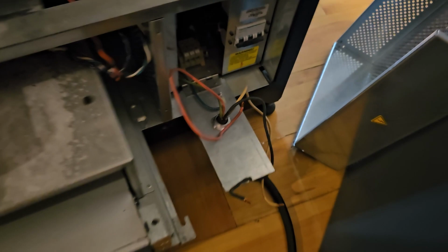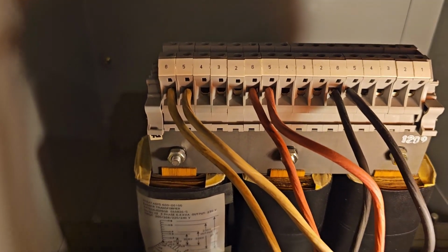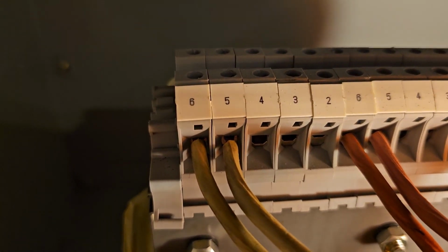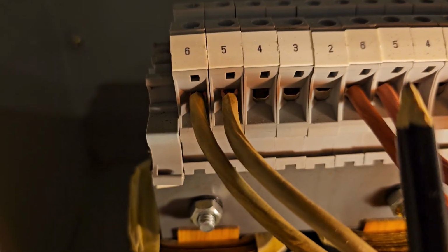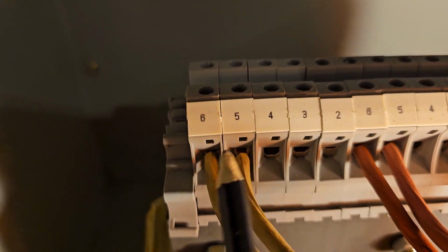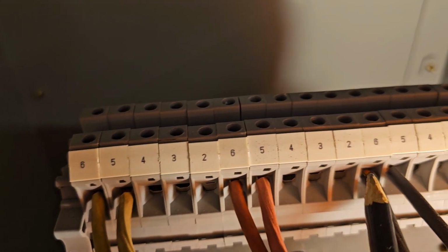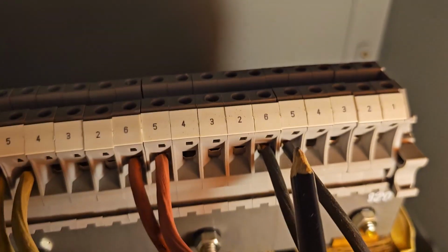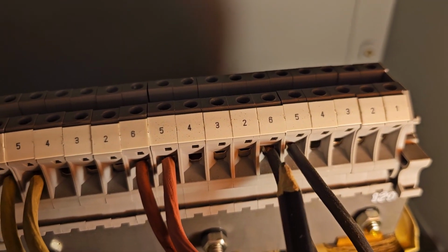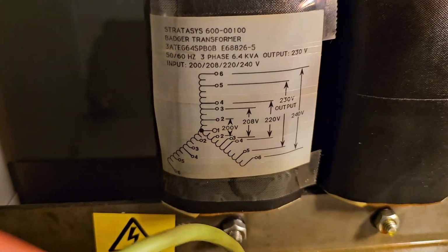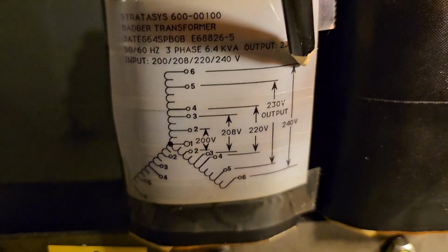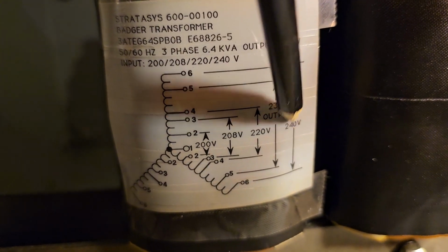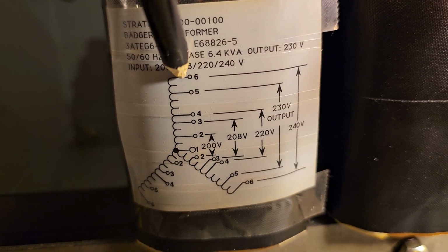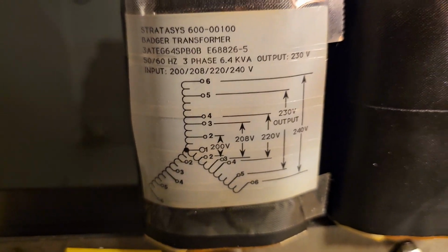So, and they're just disconnected from everything, so it's not connected to the machine. Then, in the transformer box, I moved the white wire in this first set from the second terminal connection to number 6. Did the same with the red from number 2, moved it to number 6. And same with the black from number 2, moved it to number 6. And that should be correct according to this guy here. There's the 240 volt line, should be connected to terminal number 6. You can see the number 6 there.